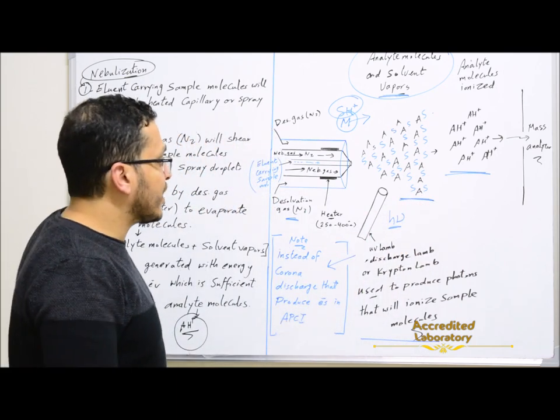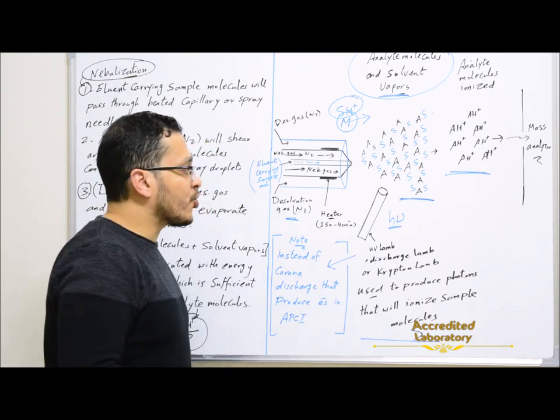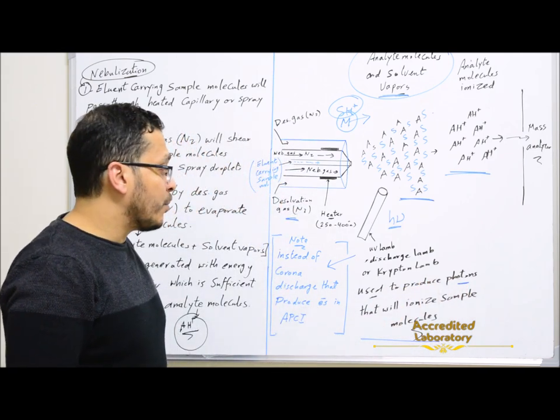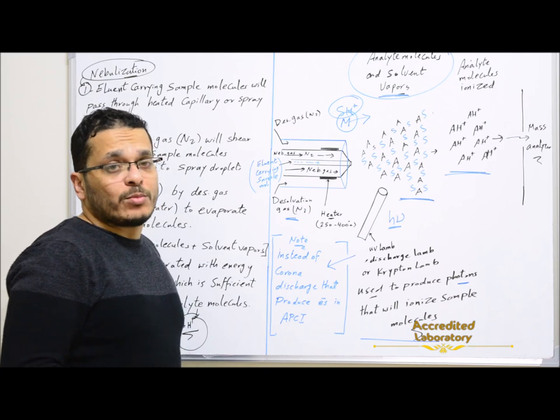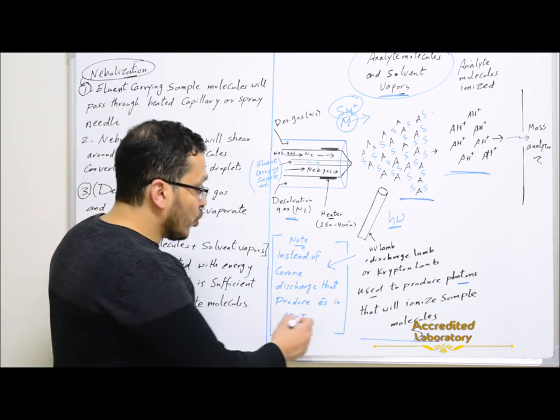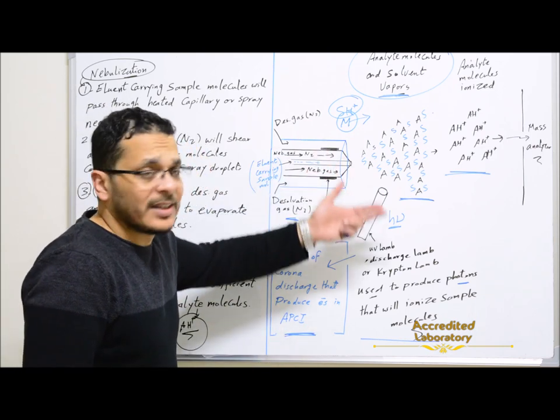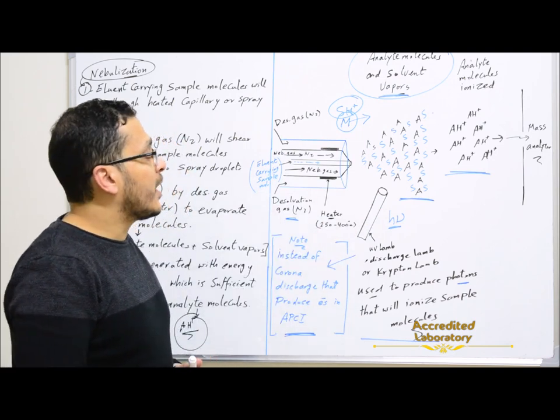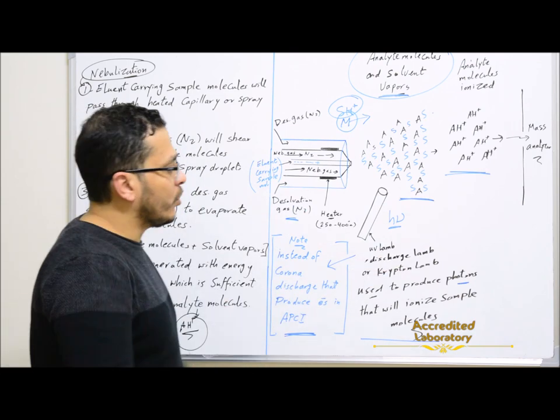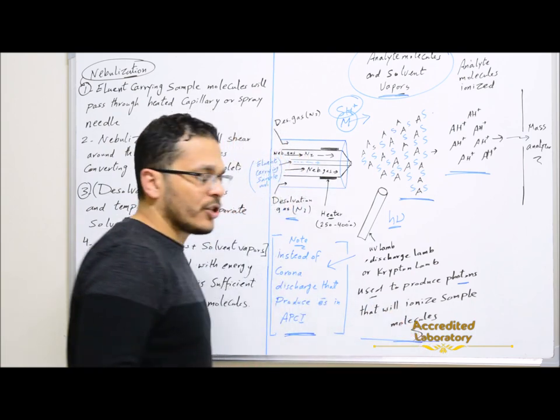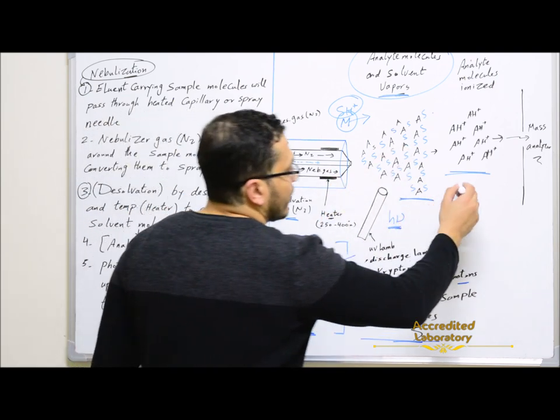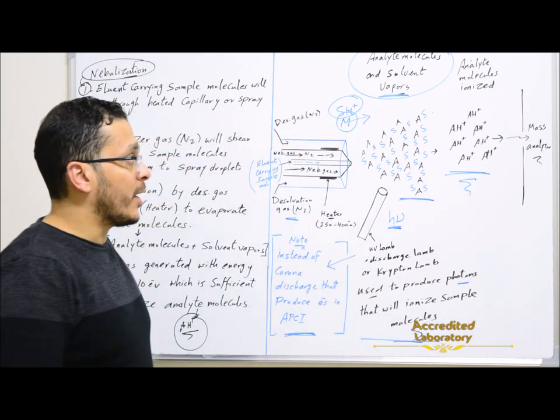Here in atmospheric pressure photo ionization, a UV lamp, discharge lamp, or krypton lamp is used to produce photons that will ionize sample molecules. This is not like in the case of atmospheric pressure chemical ionization, where we use a corona discharge to produce electrons that will ionize the solvent. After that, the solvent will transfer the ions by proton transfer to the analyte molecules, then we get analyte ions transferred to the mass analyzer. Here the UV lamp produces photons that directly ionize analyte molecules to get analyte ions transferred to the mass analyzer.